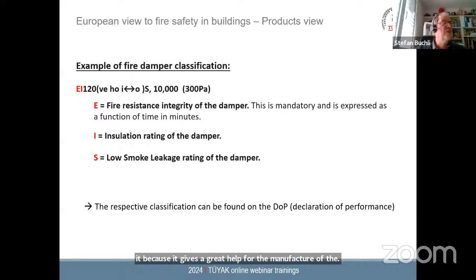Good. Talking about classification, I would like to give you a quick example of how a classification of a fire damper looks like. There are three very important characteristics of a classification. One is the criterion E, which is the fire resistance integrity of the damper. That means how long the damper can withstand a fire. And you see it here in the whole naming, E120, this is the duration in minutes. Usually you find ratings like E90, E120. These are the most common ones used in Europe, but they go up to 240 for very special applications, for example in the marine business. So this is the first criterion, which is very important.